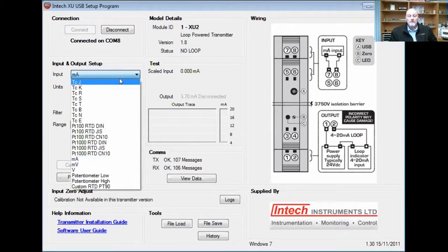Here you can see all the options: J, K, R, S, T, B, N, and E thermocouples. We also have our PT100 types. DIN is the standard that we use here in New Zealand. You can get CN10s and PT1000, but we typically stick with the DIN model. So if you're not sure which one to choose between the three, it is the DIN one. There are also milliamps, millivolts, and volts — we do up to 50 volts DC. We also have two types of potentiometer: low and high. And then you have a custom RTD if you need to.